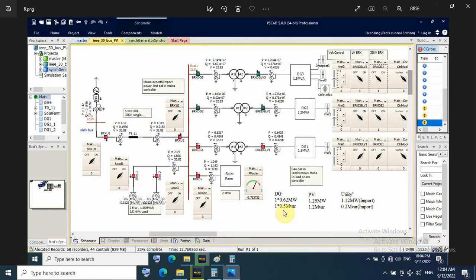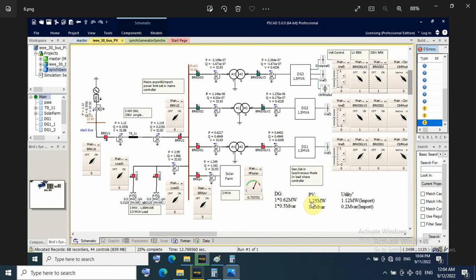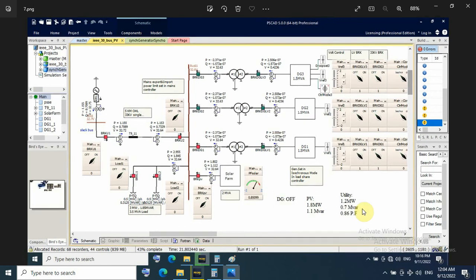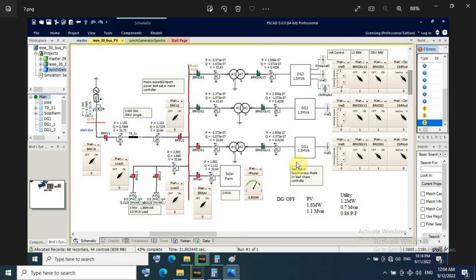So in this case I have only one DG with BV with utility. DG generates 0.6 megawatt, BV 1.25, utility 1.12 as imported power and 0.2 megavar also as imported reactive power. And if this DG shut down, then this system will be also stable because I will take 1.2 megawatt, it's still within the range for import and export limit.